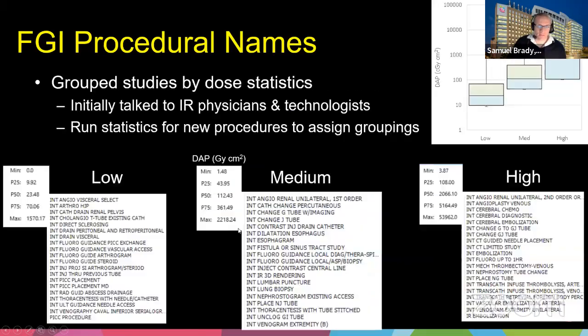So I want to give you just an example of how I approach this, specifically for interventional fluoroscopy. In this case, I needed to take a step back and understand my own procedures. So I took the data and I grouped it by radiation output. I created initially just three very large, or gross, buckets: low, medium, and high. And I went in and initially just placed the procedures that I knew had relatively low dose. And then I did the same thing for medium and high.